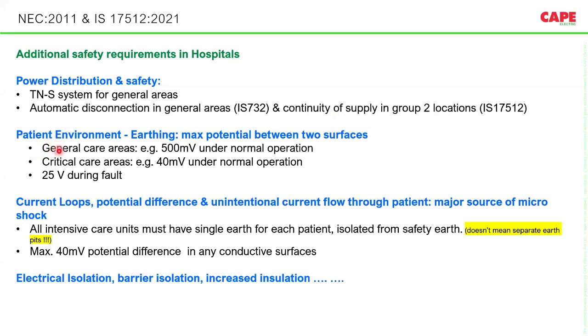Patient environment. In general care areas, 500 millivolt under normal condition. The potential difference between 2 simultaneously accessible metallic parts must be lesser than 500 millivolt in general care areas, and in critical care areas, the voltage between 2 simultaneously accessible parts should be lesser than 40 millivolt under normal condition. This 500 and 40 is under normal condition.